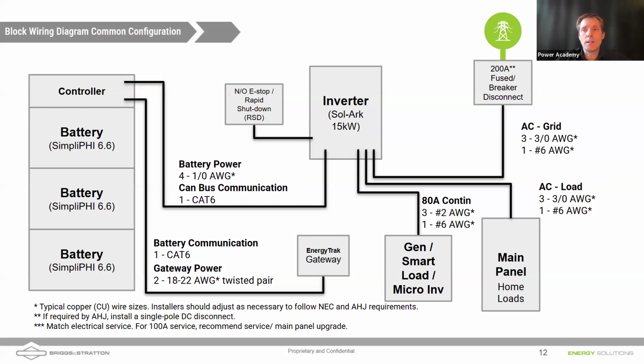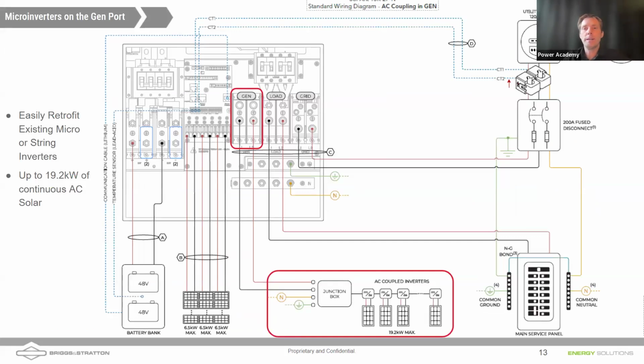Now, that doesn't mean that the inverter has enough power to power a big 4-ton AC and back that up for a long time, right? You are limited to the amount of power the inverter and the batteries are capable of supplying. And if you have a smaller battery stack, right, a three stack of our batteries is capable of delivering that full 12 kilowatts of power. But if you have a smaller stack of batteries, the batteries themselves might limit your output. So those are things to keep in mind. Again, this is a talk on programming and not a talk on sizing systems, etc. But if you're interested in those topics, please do check our upcoming trainings.